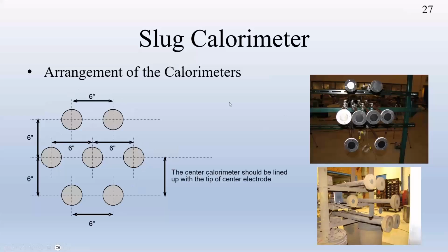So every test we put in 7 calorimeters with the matrix over there. When we do the calculation, we look at the highest temperature rise, because the damage is not based on the average temperature rise. The damage is based on the most severe temperature rise part.